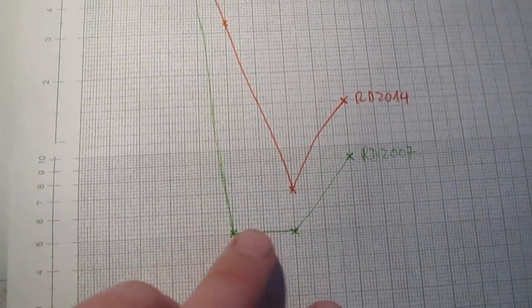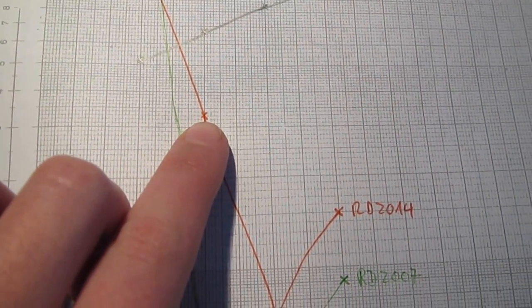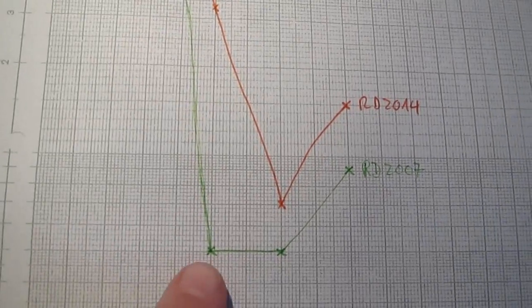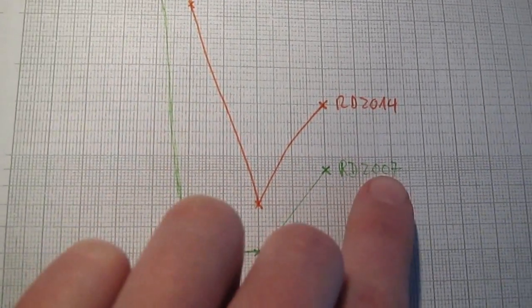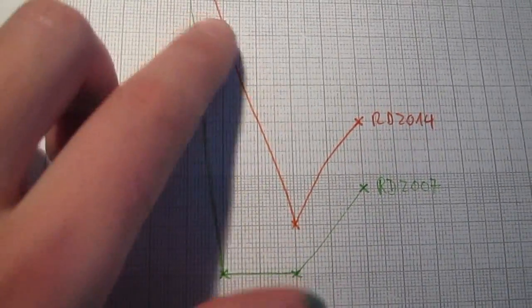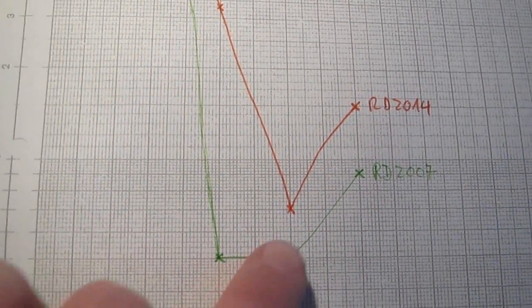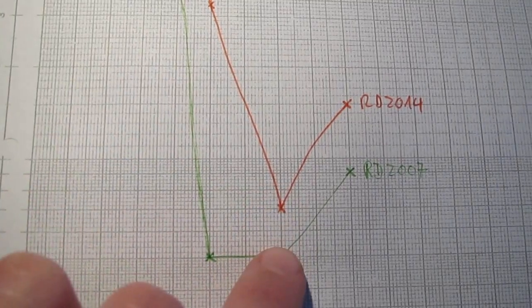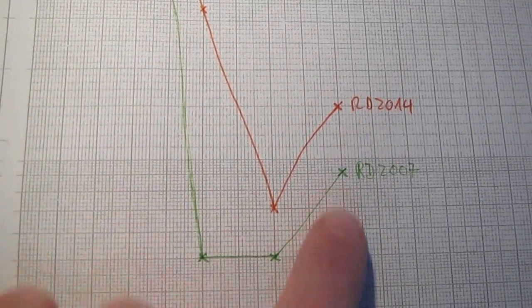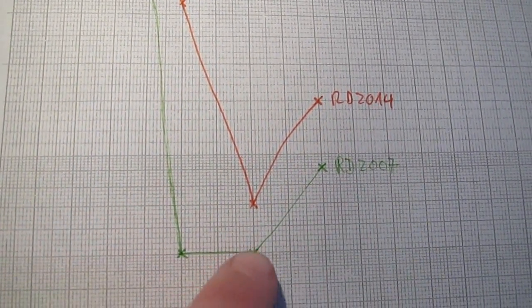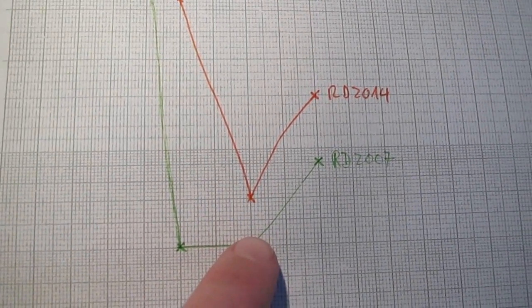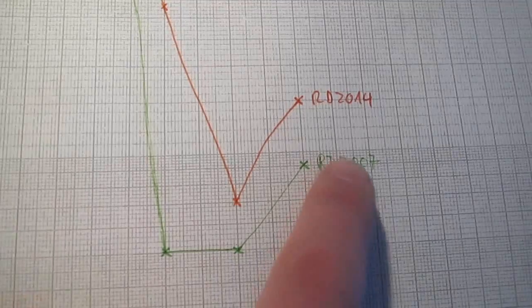Then there's a drastic decrease at detection at 60 kV, which you can see here, with the RD2007 scoring remarkably worse than the RD2014. 60 kV here, and now we have the next 80 kV and 100 kV, where the behavior is actually very similar. You can see that at 80 kV both detectors are worse than at 100 kV.